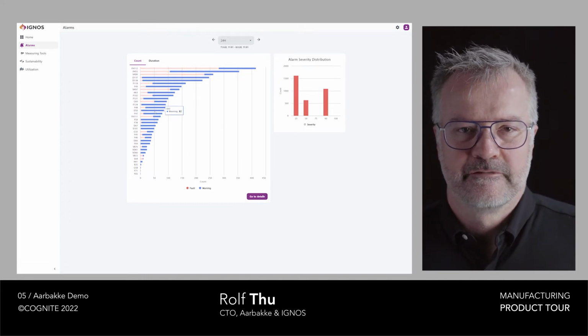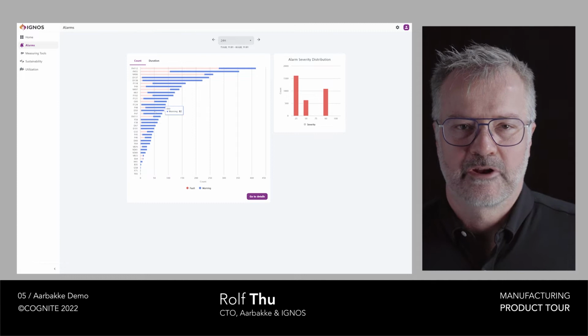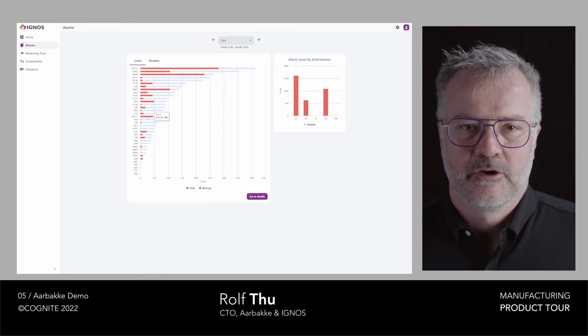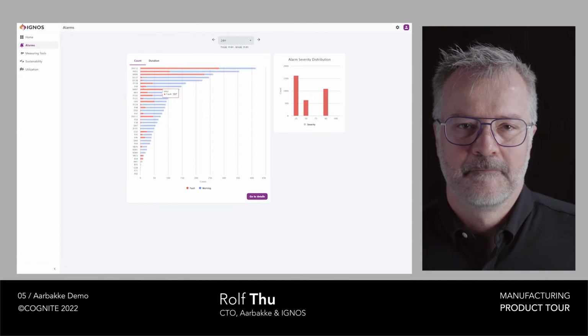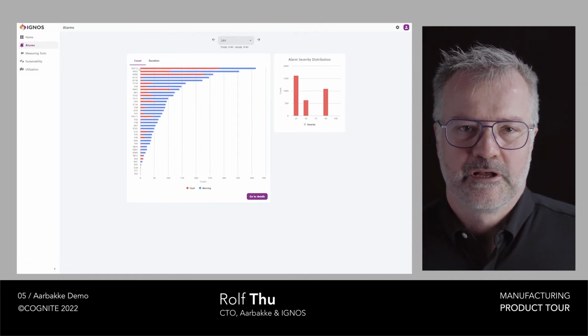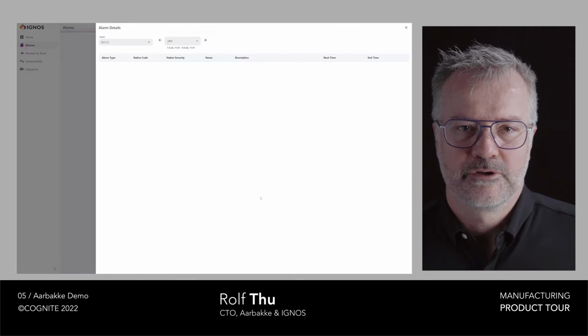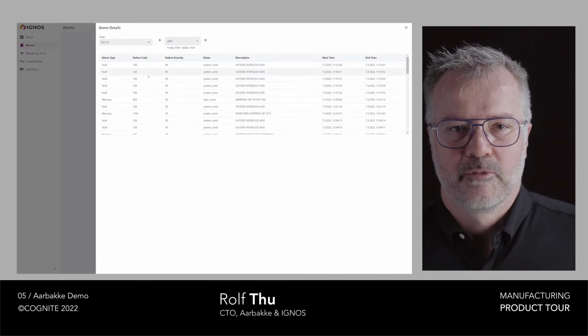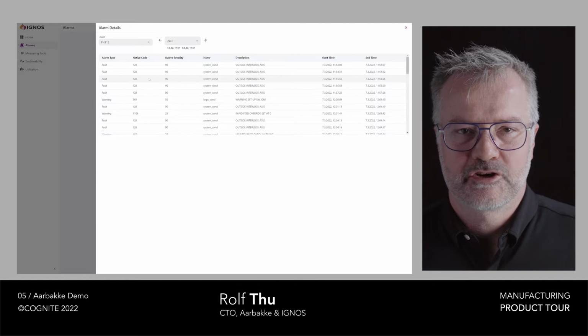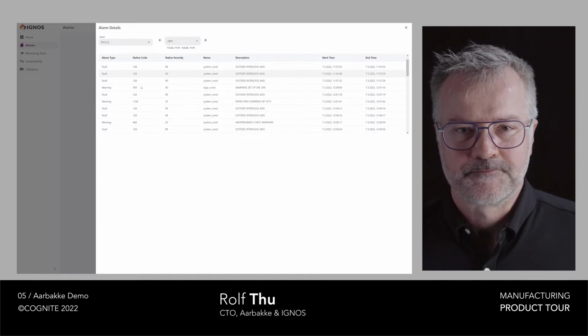They can go over to see faults, which are the alarms that actually stop the machine, and go into one of the machines to really see the details. So if you go into this machine and select one alarm code, you can see when the alarm occurred and what actually happened on the axis of the machine.